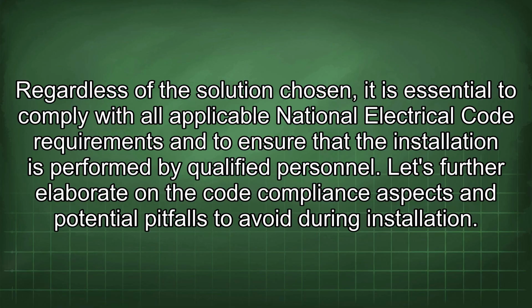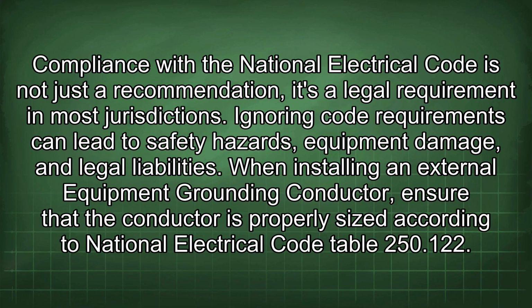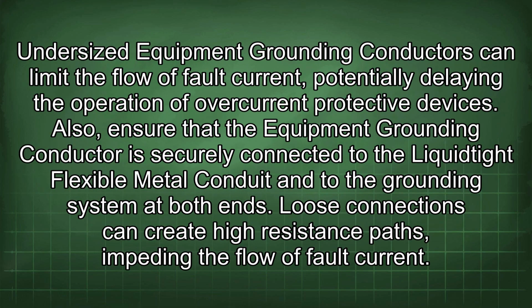Let's further elaborate on the code compliance aspects and potential pitfalls to avoid during installation. Compliance with the National Electrical Code is not just a recommendation, it's a legal requirement in most jurisdictions. Ignoring code requirements can lead to safety hazards, equipment damage, and legal liabilities. When installing an external equipment grounding conductor, ensure that the conductor is properly sized according to National Electrical Code Table 250.122. Undersized equipment grounding conductors can limit the flow of fault current, potentially delaying the operation of overcurrent protective devices.